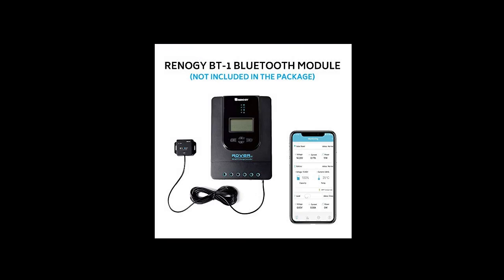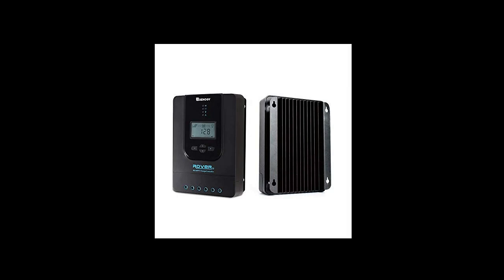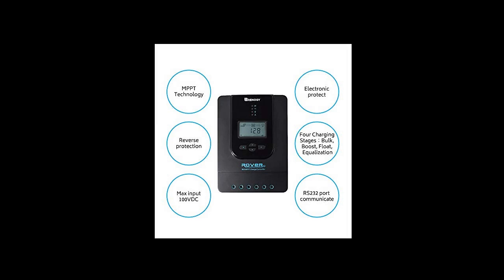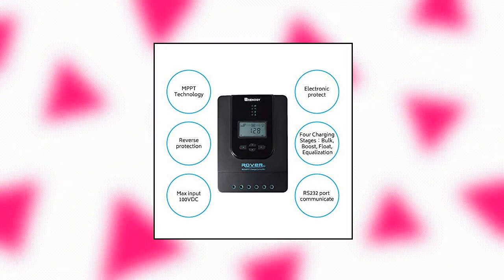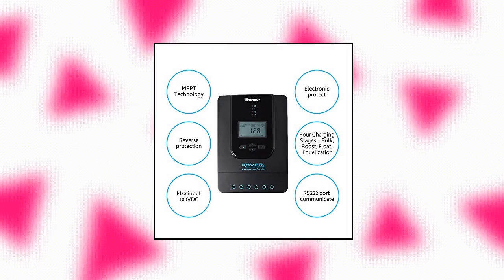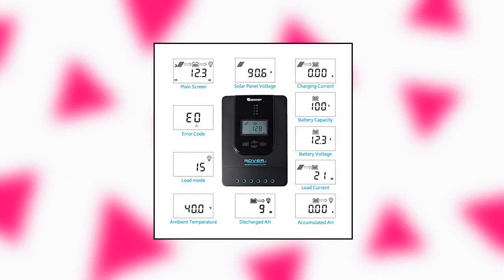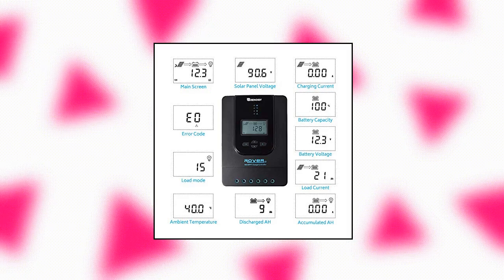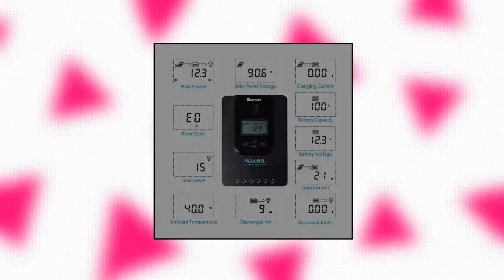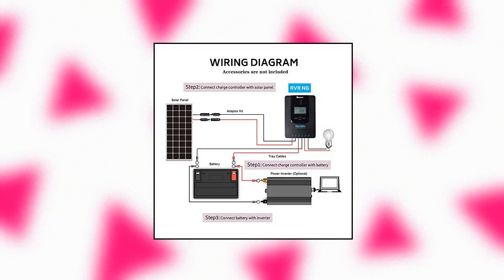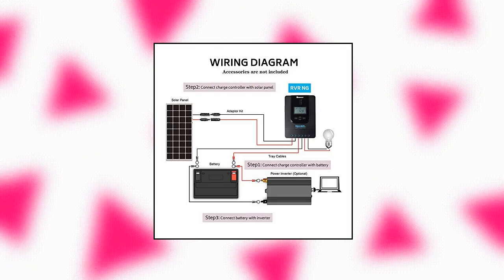fluctuate all day. Automatically detects 12 volts or 24 volts DC system voltages, and the LCD screen and multiple LED indicators display the solar charging and battery operation information, customizable parameters, and error codes meant to safeguard your system. The self-diagnostic capability can assess and protect against reverse polarity, battery overcharging, battery overdischarging, overload, short-circuiting, and reverse current.